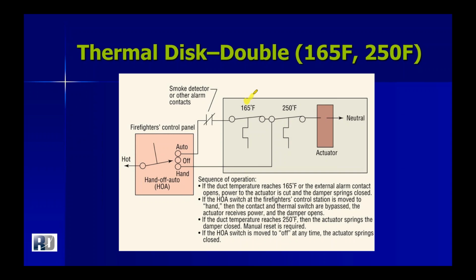But if that were to trip, or even the smoke detection going off, if the firefighter wanted that damper to go open, they would actually have the ability to put that in hand and, again, re-energize the actuator to open it. But there is a fail-safe 250-degree thermal link that would be utilized to say, hey, this is just past even what the firefighter wants it to be, and it's, again, going to be recommanding the actuator closed.